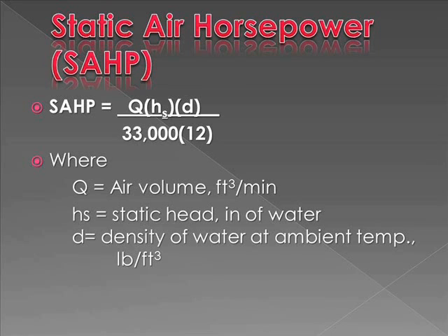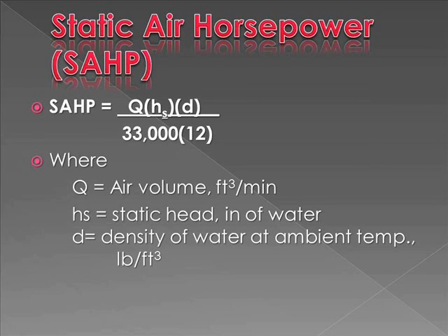Static air horsepower or SAHP is determined by the given formula: air volume times static head times density of water at ambient temperature, all over 33,000 times 12.